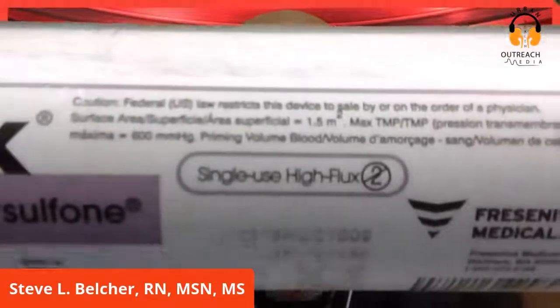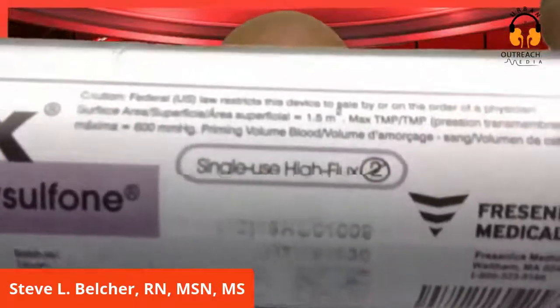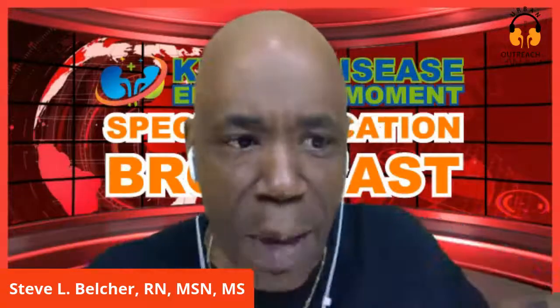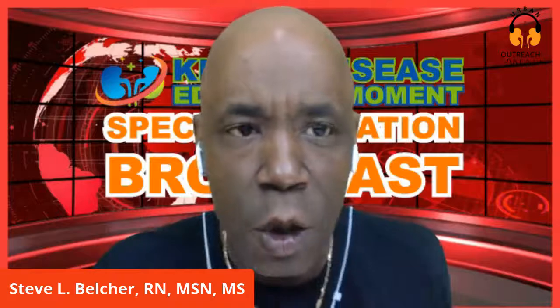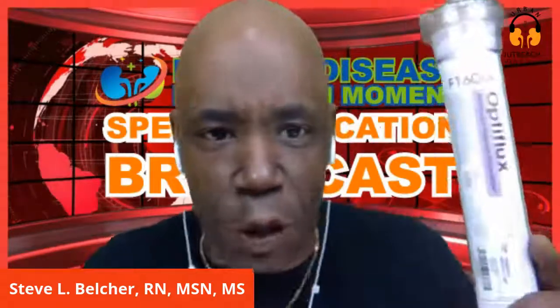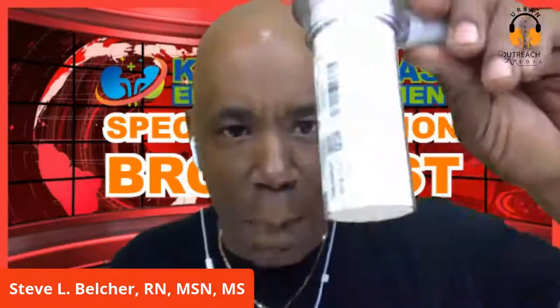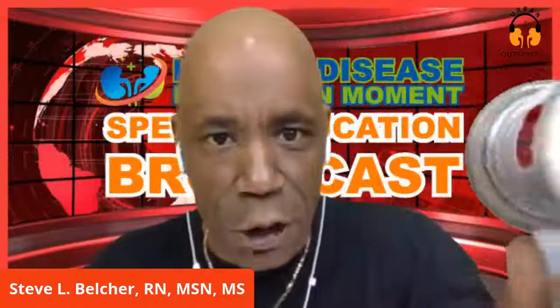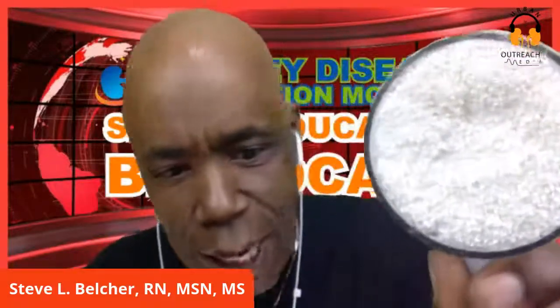People and companies are still reusing dialyzers - you can see it for yourself. Single use means throw it away after you're done. Don't take it back and put formaldehyde or some other germicide in the filter for the next treatment. Now, this is the same filter but cut in half to show you the inside.